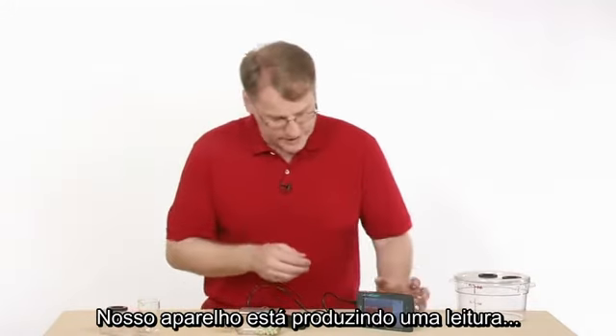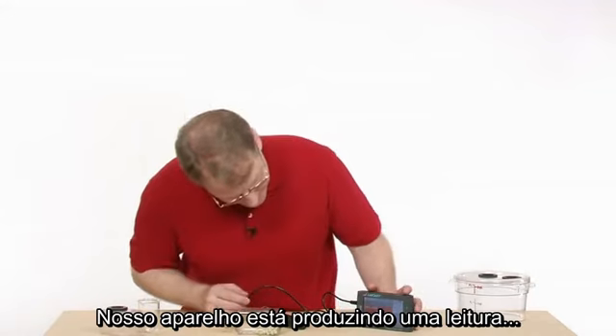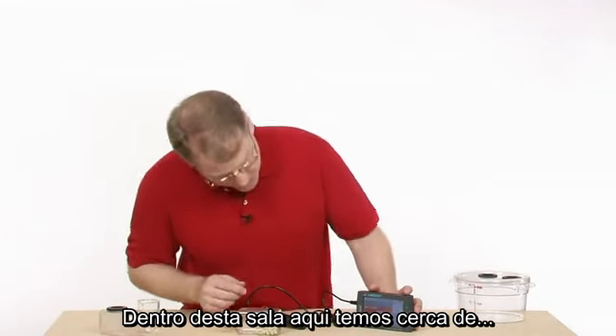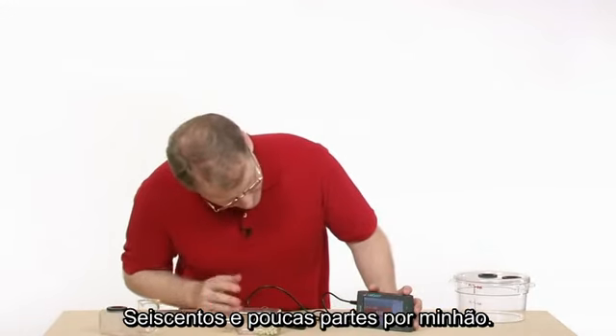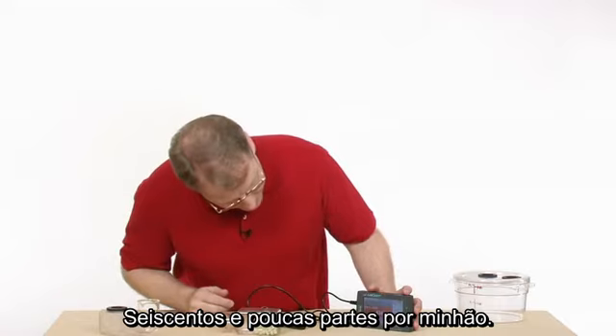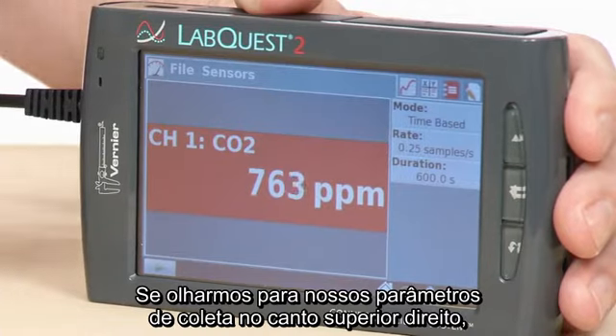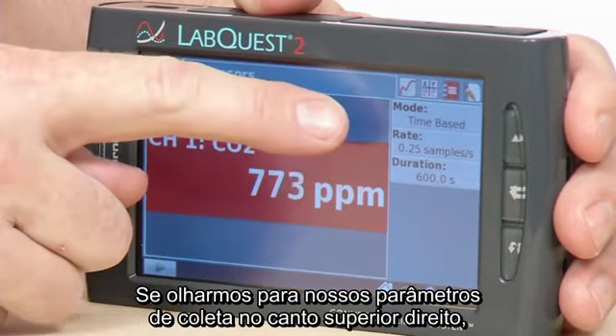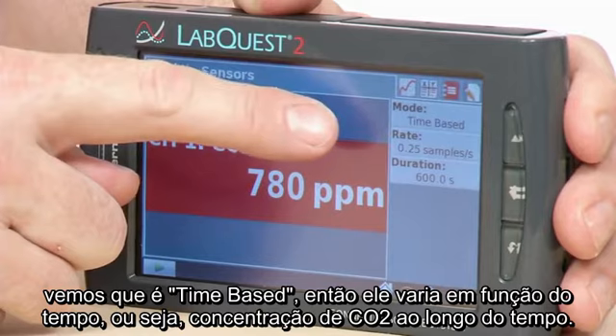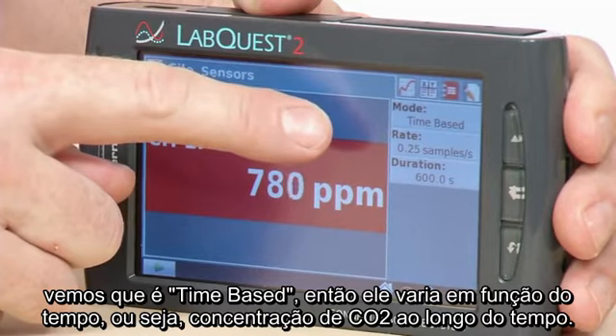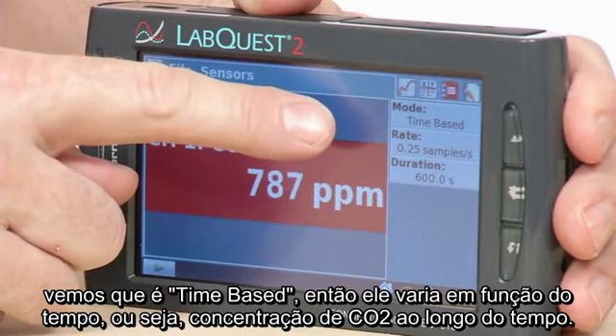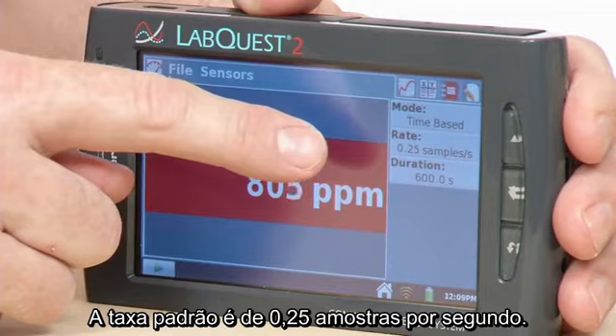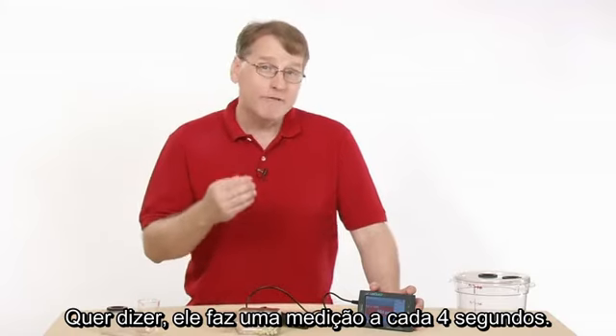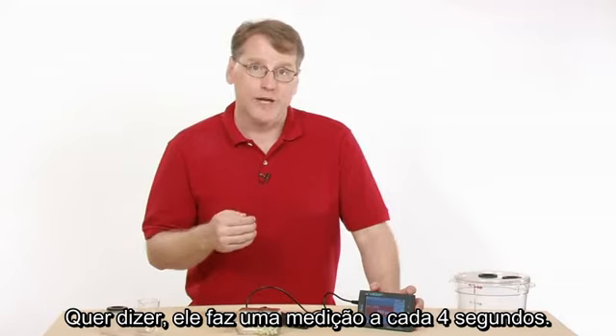So our unit is now reading here, and so inside our room here we've got about 600 and something parts per million. So if we look at our collection parameters in the upper right corner here, we see time-based, meaning that it is a variable as a function of time, so CO2 concentration with time. The default rate is 0.25 samples per second. It's actually every 4 seconds it's going to make a measurement.